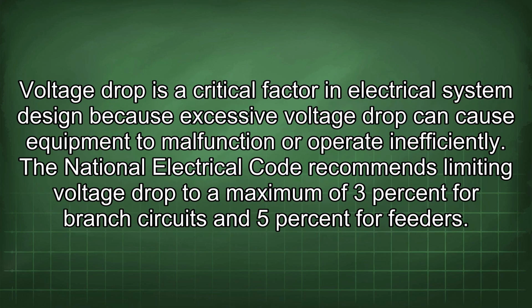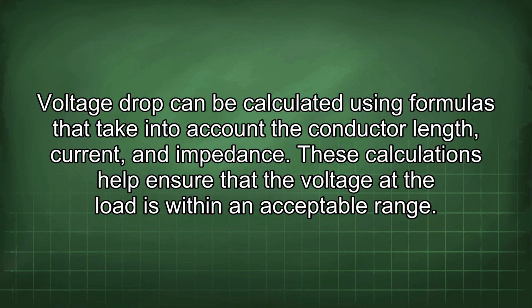Voltage drop is a critical factor in electrical system design because excessive voltage drop can cause equipment to malfunction or operate inefficiently. The National Electrical Code recommends limiting voltage drop to a maximum of 3% for branch circuits and 5% for feeders. Voltage drop can be calculated using formulas that take into account the conductor length, current, and impedance. These calculations help ensure that the voltage at the load is within an acceptable range.